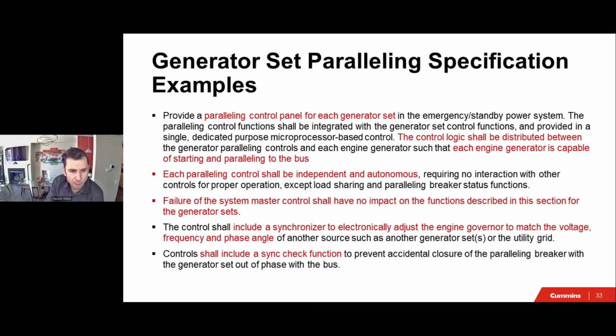To help you with that, I wanted to provide a specification language, but it's like I said, and you probably know this because you're designing a lot of these systems, the specs are about 37 pages long. Maybe sometime this year we'll dedicate a whole session to specs for paralleling controls and paralleling switchgear. But some of the things you want to have in there are a paralleling control panel for each generator set. You want the control logic to be distributed, and each generator set capable of starting and paralleling on the bus independently. We don't want a master controller to do so, because if that one fails, that entire fleet of gensets will fail, will not start and will not parallel.